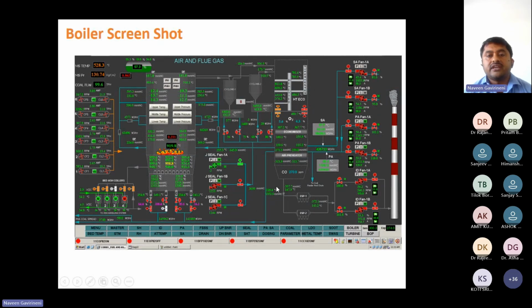Okay. Next, while coming to each and every part I will explain. Just have a look. This is the bed ash cooler arrangement. That means drained ash is going through the bed ash cooler. There is a J-seal fan arrangement for supplying air at this cyclone. Cyclone concept, you know: at the outlet of the furnace there are minor particles with the flue gas. Those particles have energy content, that means heat value. If we leave those particles to the atmosphere, there is a loss, a chance of loss of ignition. So for that purpose there is the cyclone concept.